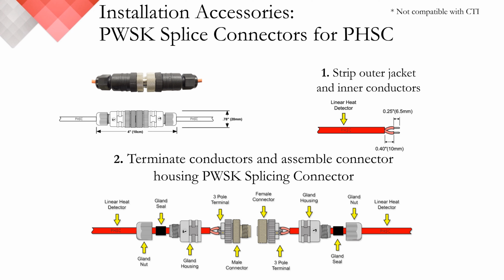In addition to the PWSC splice connector, we also offer our PWSK splice connector. This is the threaded assembly providing a watertight and oil-tight seal that grips the Protectowire Linear Heat Detector securely. This kit provides a simple method of making inline splices while allowing easy disassembly for service and proper environmental protection without the use of a zone box. Like the PWSC connector, this splice connector is specific to our PHSC and PLR series detectors.